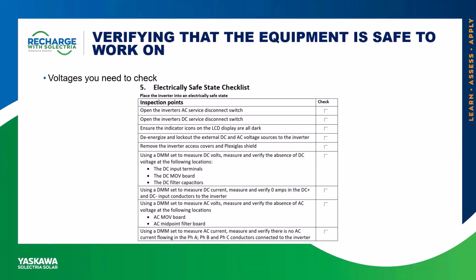This is in a particular order. We want to remove the AC component of the voltage first, then the DC component, and then make sure all the LEDs, panels and lights are off. But not just that - we want to go out and find those combiners, turn those off and lock those out too, so we don't accidentally re-energize something if we forgot about it.